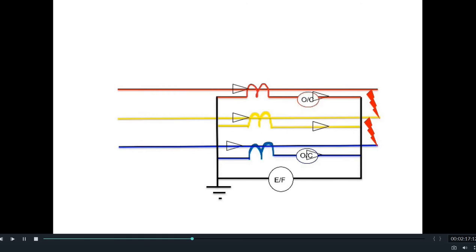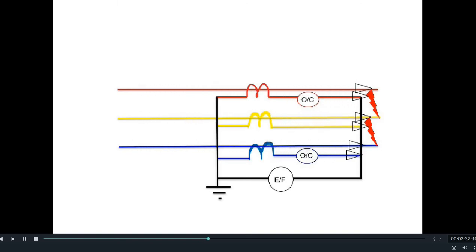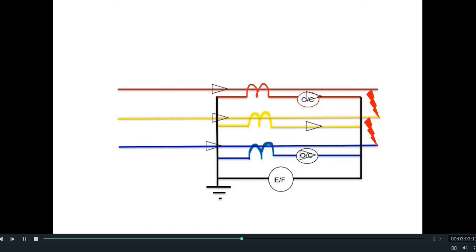If there is overloading in the transmission line, overcurrents will flow through the CT secondary in R, Y, and B phases. As overloading is considered a three-phase phenomenon, a similar thing happens in case of three-phase line faults. The overcurrent relays, being above their plug setting, will actuate and trip the circuit, isolating it from the fault. However, since the vector combination of R, Y, and B in star remains nearly zero, almost no current flows through the earth fault relay, so only the overcurrent relays will trip in this case.